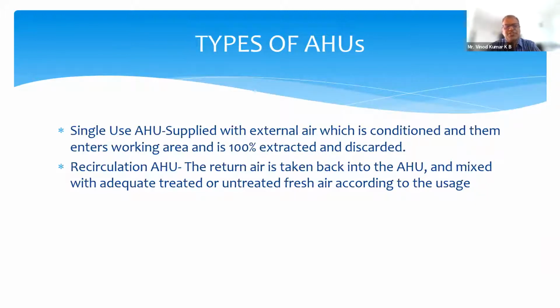But things have changed over the years. It's a very good system because it has the highest level of contamination control as compared to the second type of AHU, which we call the recirculation AHU. But at the end of the day, you need to save energy because 100% fresh air systems are very high in cooling loads as compared to the recirculation AHUs. So over the period of years, a number of studies have happened and they have come across the kind of recirculation AHUs that have to be used in the various kinds of application in the hospital. Various kinds I'm trying to say is you have operating rooms, you have ICUs, you have bone marrow transplant rooms, you have various kinds of usages.